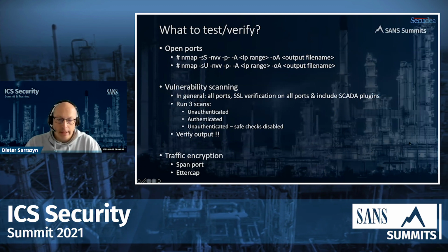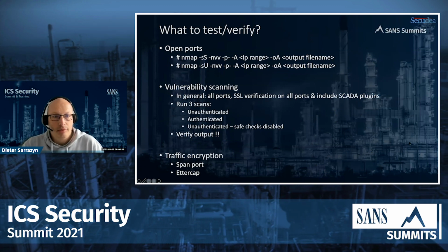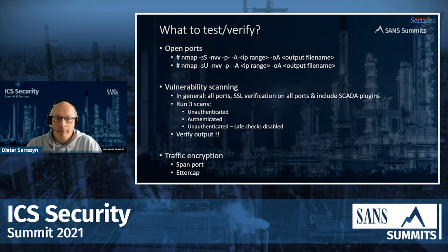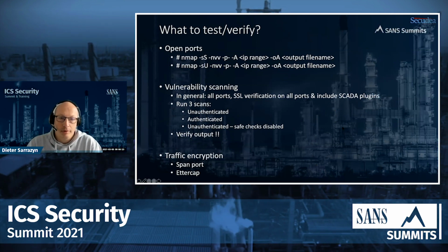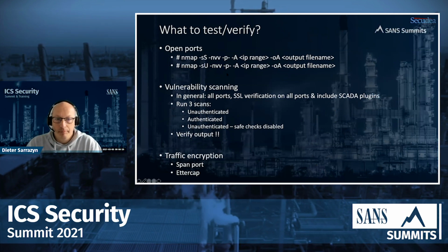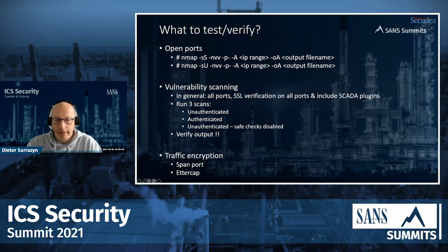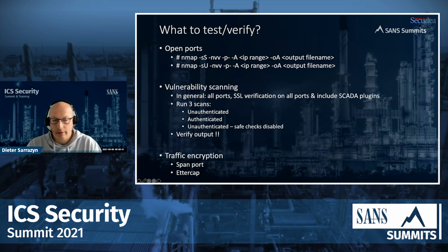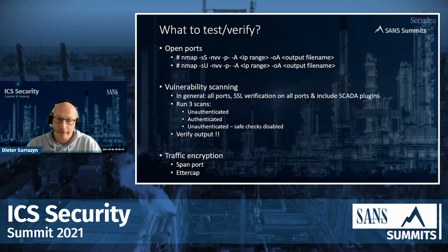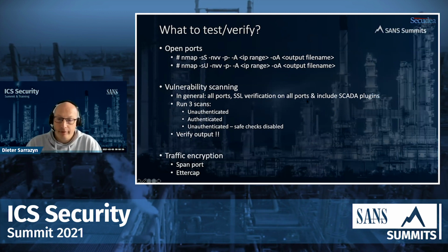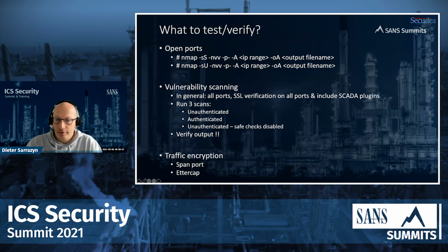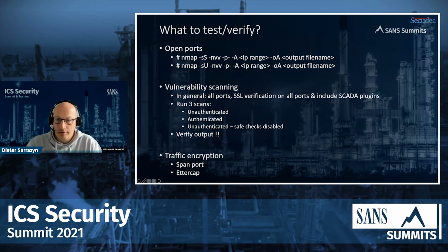On the following slides, I give you some more technical information on how to do testing and verification. So open ports, you should make sure that you include both TCP and UDP on all ports. On vulnerability scanning, you should make sure that you scan all ports, you perform SSL verification on all ports. And depending on the vulnerability scan you use, you should make sure that you include SCADA plugins.